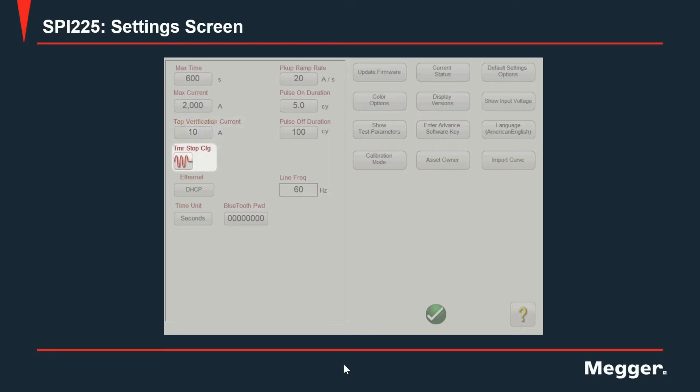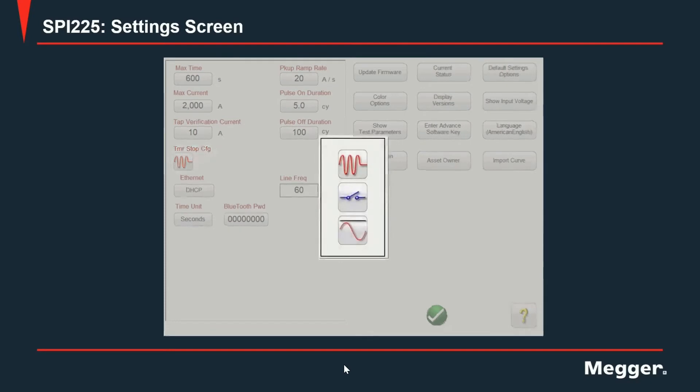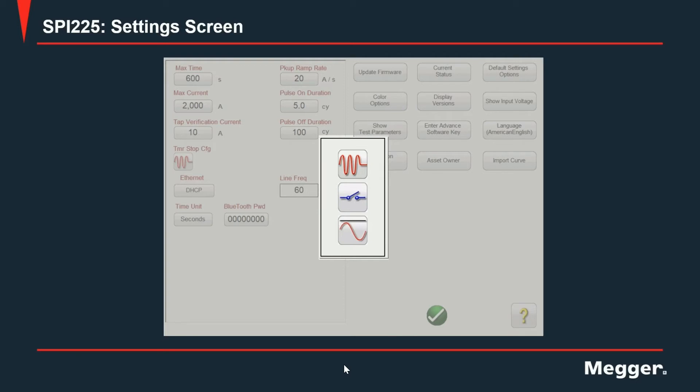Next, we have timer stop configuration. On this setting, we have three different options. The first, current activate, being the first and the most common option used as this will stop the timer whenever the circuit connected to the output is interrupted or in other words, whenever the circuit breaker connected to the output opens the contacts.